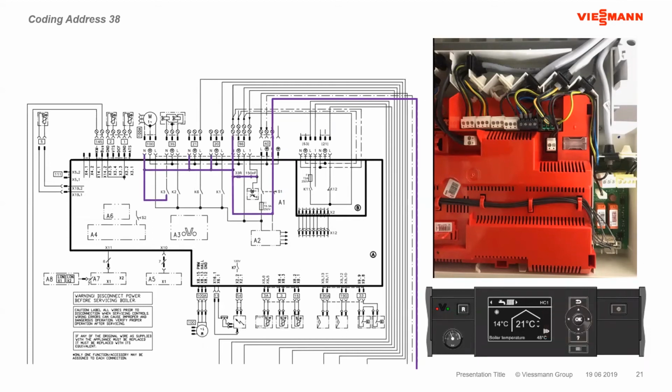Anyway. So now we've got that power button closed. You can see in purple where all that stuff ties off to. So there's our neutrals. There are relays in here that are going to close based on combustion. So these are going to close to power things like the gas valve and the fan motor, etc. Any pump outputs, so there's the domestic pump and the boiler pump, 120 pump outputs, they're up there as well. So we switch those off of 120 volt up at the top.